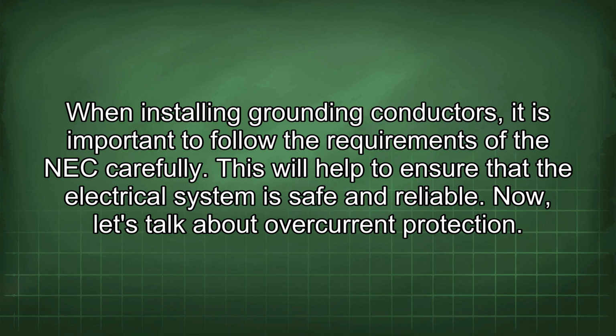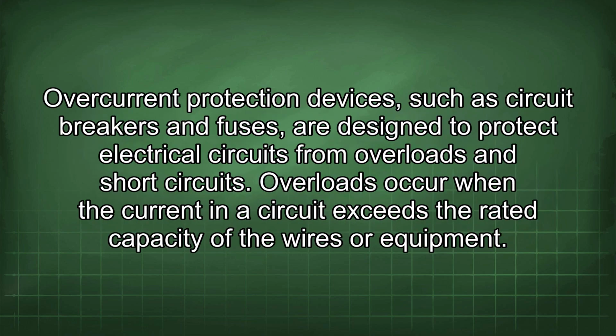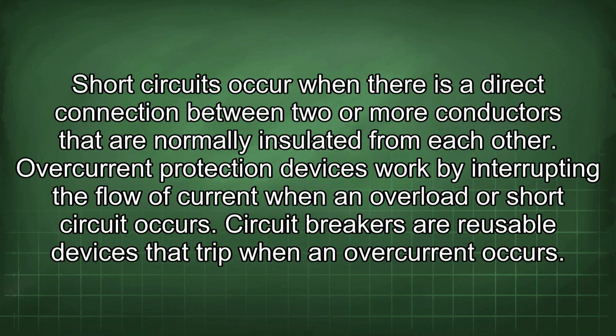Now let's talk about overcurrent protection. Overcurrent protection devices, such as circuit breakers and fuses, are designed to protect electrical circuits from overloads and short circuits. Overloads occur when the current in a circuit exceeds the rated capacity of the wires or equipment. Short circuits occur when there is a direct connection between two or more conductors that are normally insulated from each other. Overcurrent protection devices work by interrupting the flow of current when an overload or short circuit occurs.